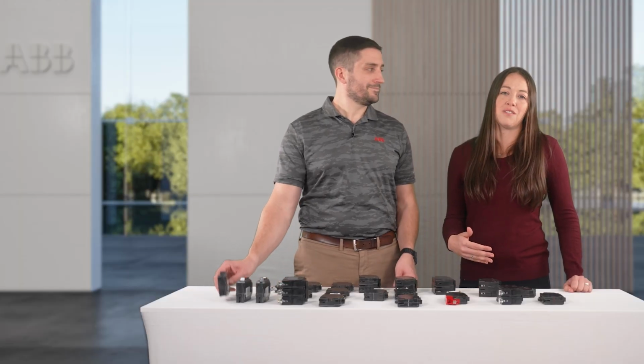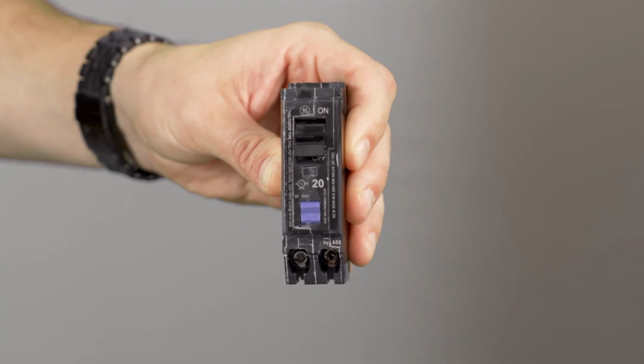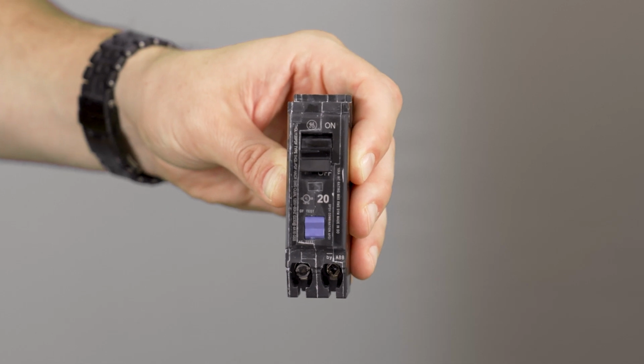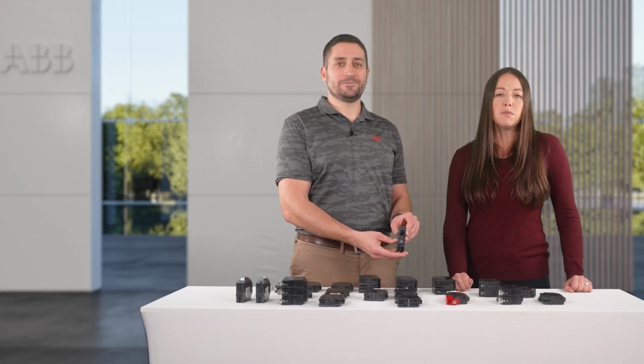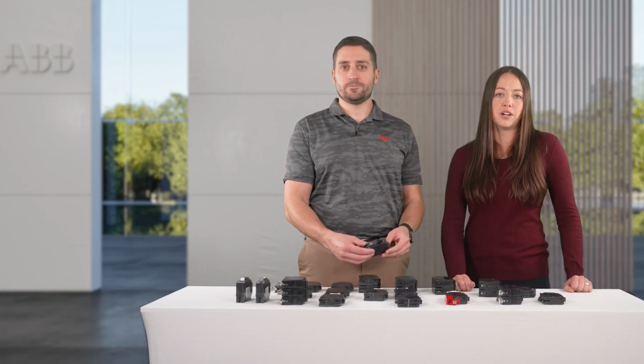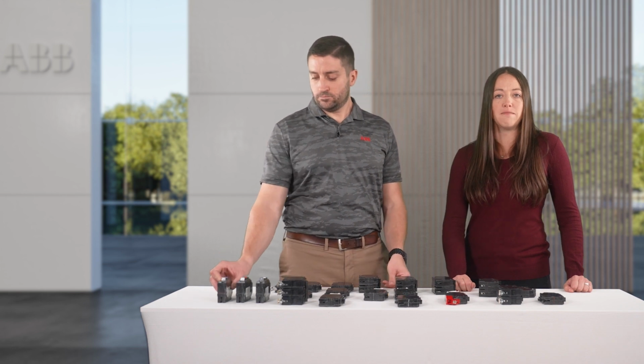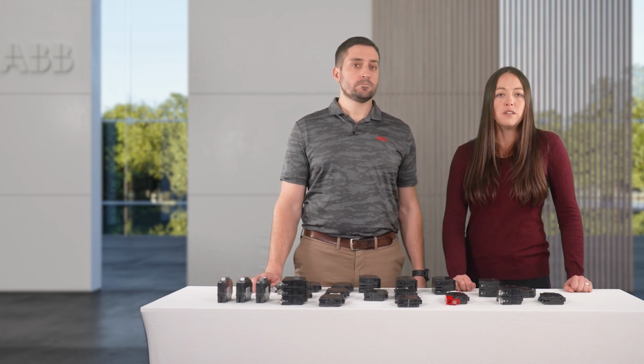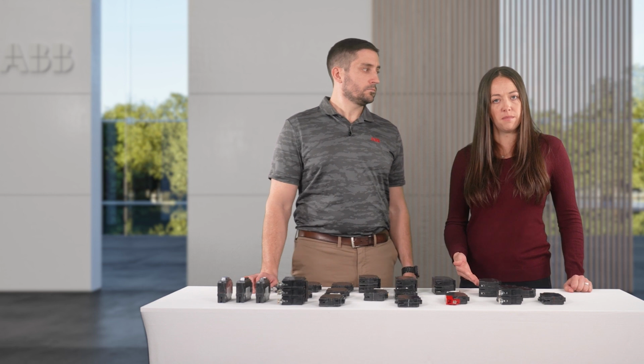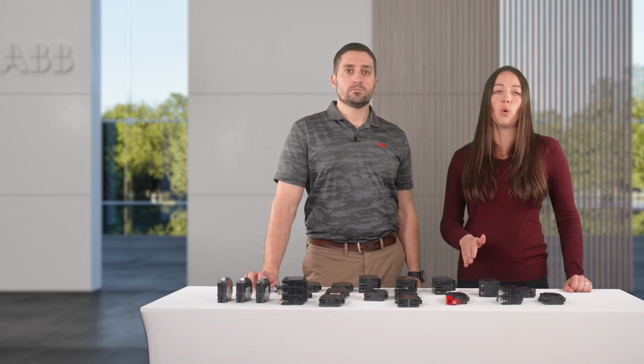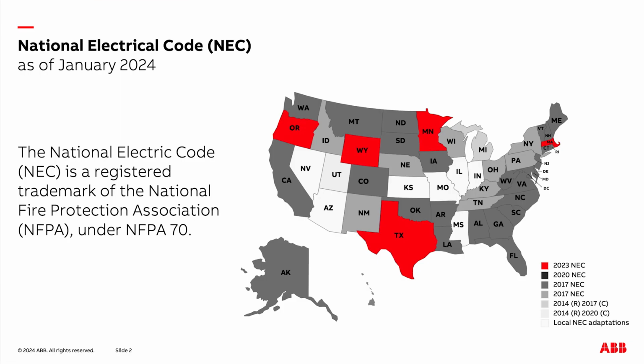Dual function circuit interrupters protect against overloads, short circuits, parallel arcs, series arcs, and ground faults. The ground fault protection utilized in a dual function breaker protects against ground leakages of 5 milliamps and greater. Because dual function breakers have ground fault protection within them, they cannot be on a shared neutral or the breaker will trip.